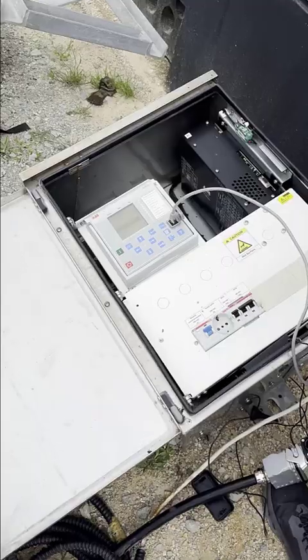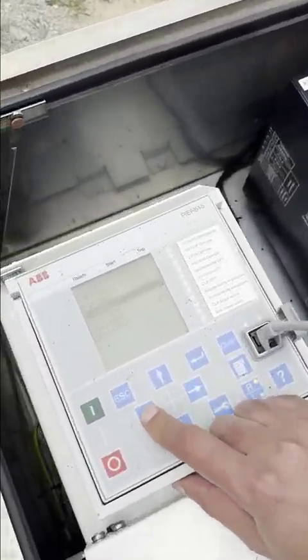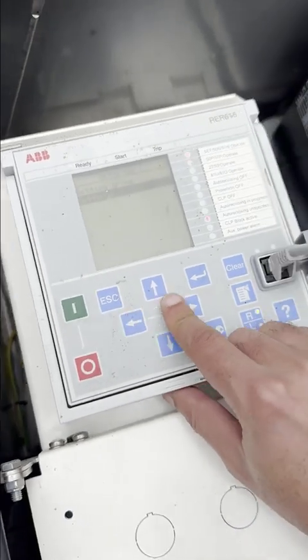Okay, we have also a second stage, which is a 50B. As you can see, it's on, and here is the number of start phases is 3 phases, and the setting group 1, as you can see. So the start value is 0.05 multiplied by IN, and it's IEC normal inverse. Okay, so from the relay HMI also you can get this value, from the setting.